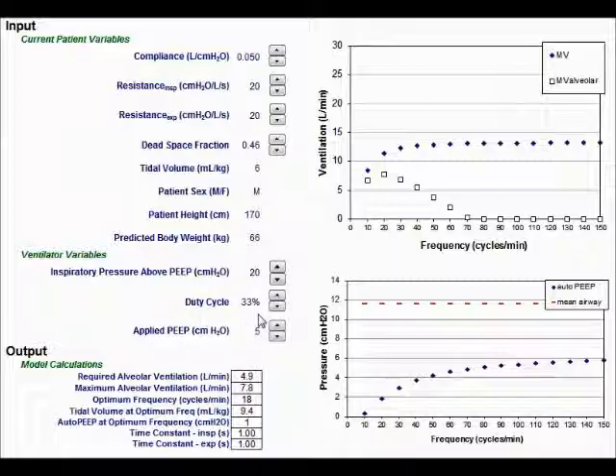And here's my duty cycle. It's a 33% duty cycle, which is an IE ratio of 1 to 2. So that's my setting.